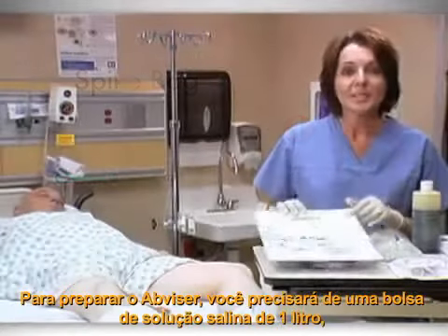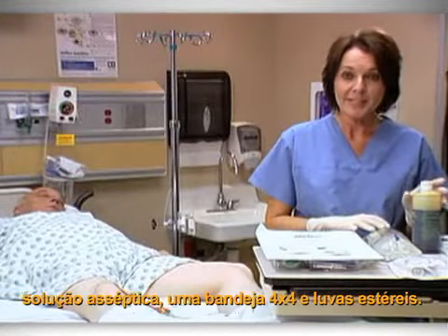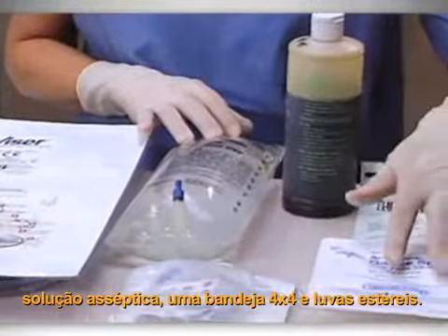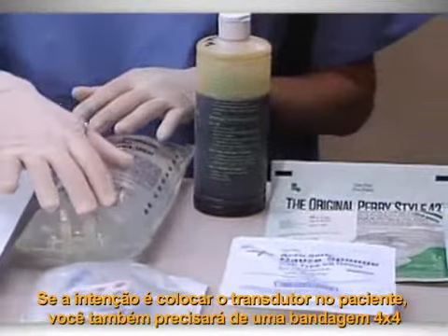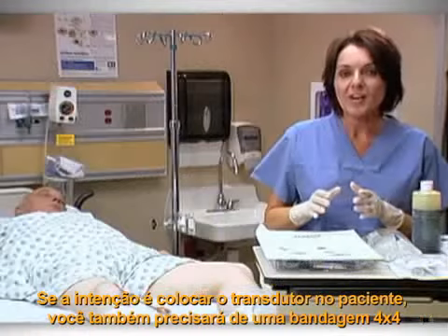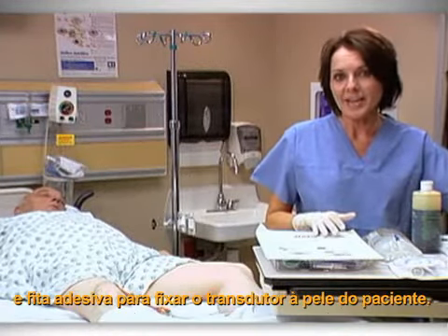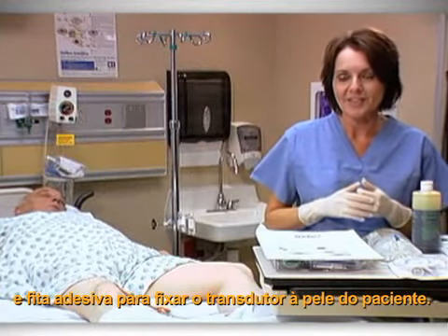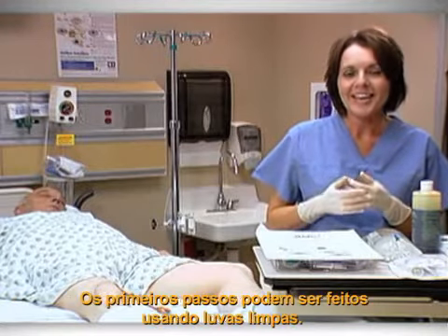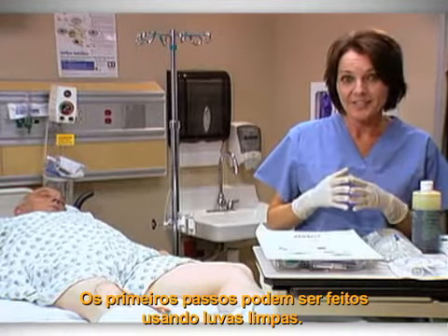To set up the Abviser, you will need a 1-liter saline bag, an aseptic solution, and a 4x4 tray with sterile gloves. If you intend to patient mount the transducer, you'll also need a 4x4 pad and some tape for attaching the transducer to the skin of the patient. Let's get started. The first steps can be done using clean gloves.